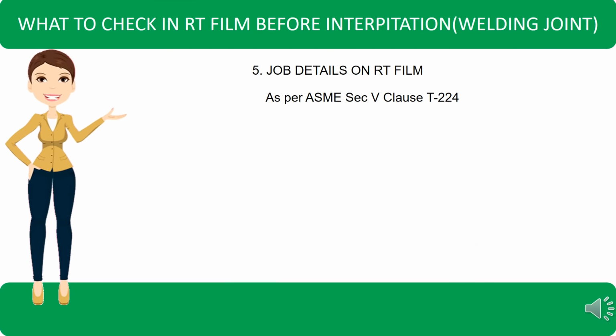The fifth factor is job details on radiographic film. As per ASME Sec V Clause T-224, a system shall be used to produce permanent identification on each radiograph which is traceable as per contract or company norms.